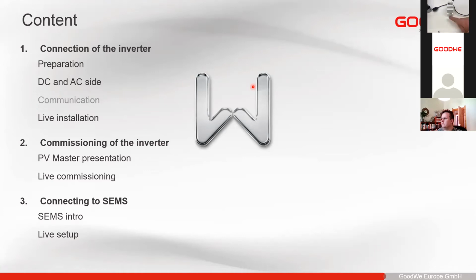On the bottom side here, you have the voltage sense. And here, the important thing to know is that the order here is reversed. So please make sure that you check here on the bottom side. Here you even see neutral, line 1, 2, and 3. And on the top, you only have numbers like this, but it also says on the CTs which one it is. If you have any questions, as I said, here on the side of it, it also says how to connect it. There's a diagram explaining.